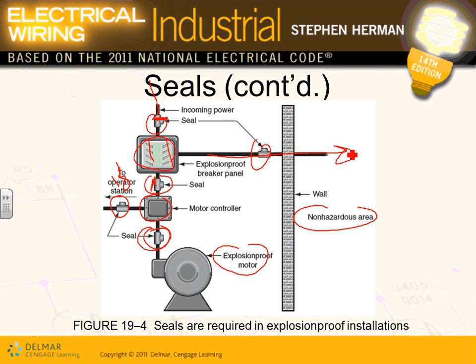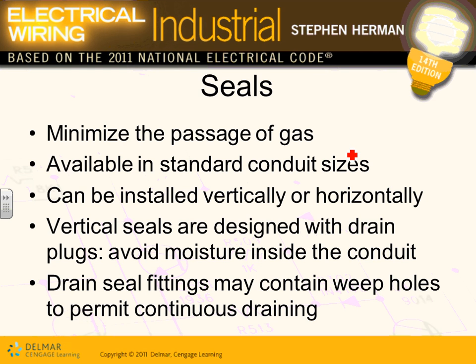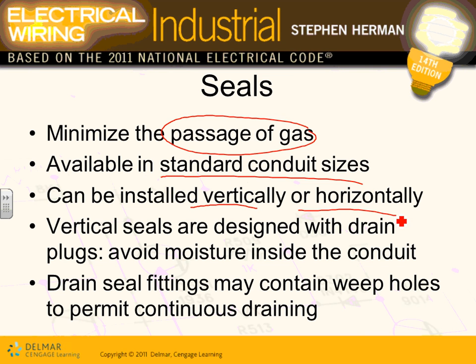There's a lot of sealing in these areas. The purpose of sealing is to prevent the gas and the vapor and the dust from getting into the electrical equipment and creating a fire. Okay, so here's my seal. So minimize the passage of gases. That's why we seal. They are available in standard conduit sizes and oversized too. You can put them vertical and horizontal. I'll show you in a second.